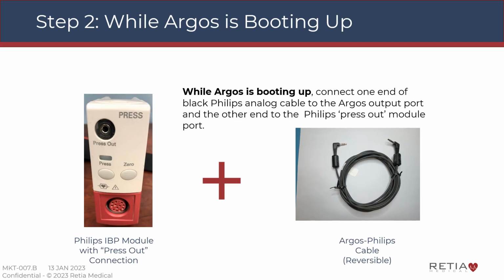Step 2. While the Argos is booting up, connect one end of the black Philips analog cable to the output port located on the side of the Argos monitor, underneath the power button, and the other end to the Philips press out or pressure out module port, as shown here.